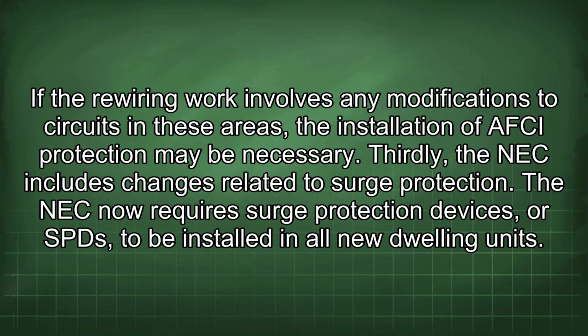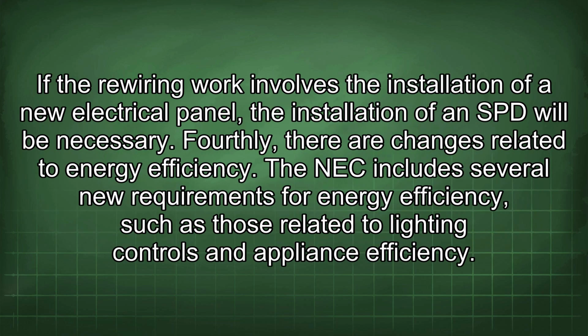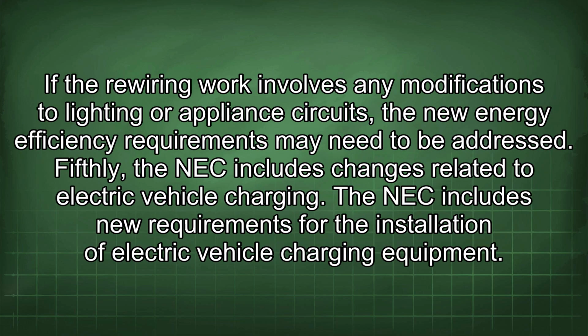Thirdly, the NEC includes changes related to surge protection. The NEC now requires surge protection devices, or SPDs, to be installed in all new dwelling units. If the rewiring work involves the installation of a new electrical panel, the installation of an SPD will be necessary. Fourthly, there are changes related to energy efficiency. The NEC includes several new requirements for energy efficiency, such as those related to lighting controls and appliance efficiency. If the rewiring work involves any modifications to lighting or appliance circuits, the new energy efficiency requirements may need to be addressed.